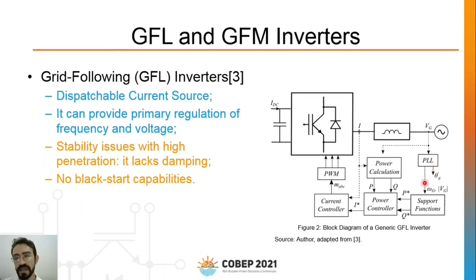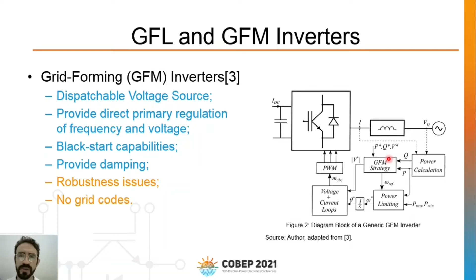Grid-forming inverters, on the other hand, are dispatchable voltage sources. So in these inverters, the control objective is to define the voltage at the output of the inverter. And these inverters provide primary regulation of voltage and frequency in a more direct way, since the voltage and phase are directly defined by the control, which also provides the feature of black start capability. One important point about these inverters is their capability to provide damping to the grid. A challenge for these inverters is their robustness issues, since, for example, they still have problems with peaks of current during transients of loads and voltage. And also there are no grid codes for these inverters.